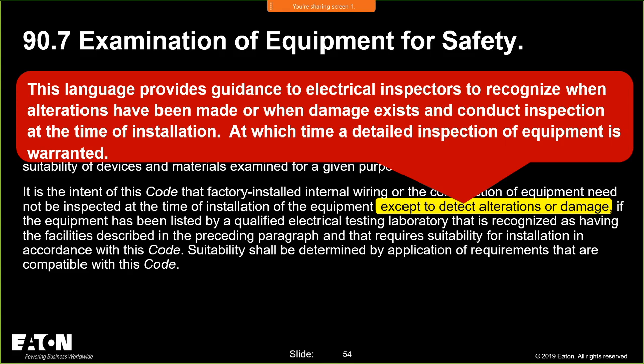This is when the inspector could say, look, you're going to need a field evaluation because you cut some holes in the back of this panel that you shouldn't have, or you tapped that bus, which is not listed, not shown as a location on the bus to be tapped. Things like that. This is what drives field evaluations and changes.